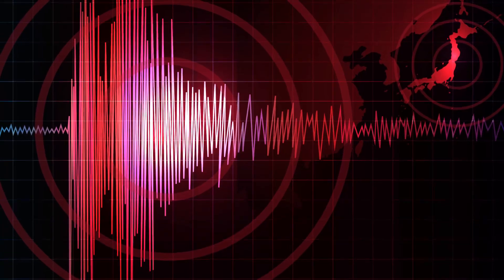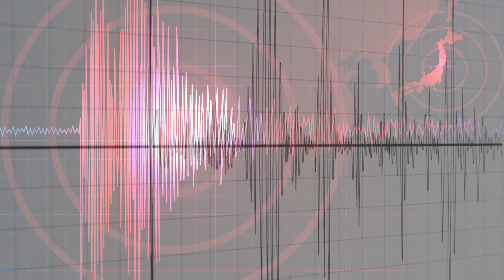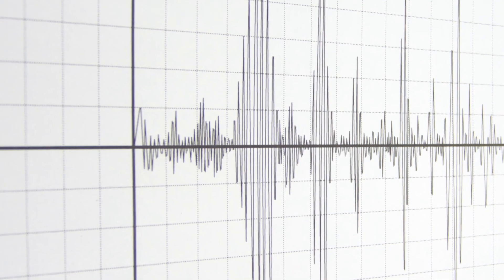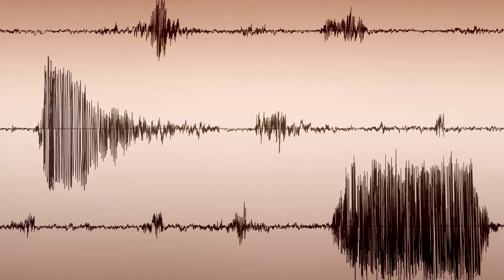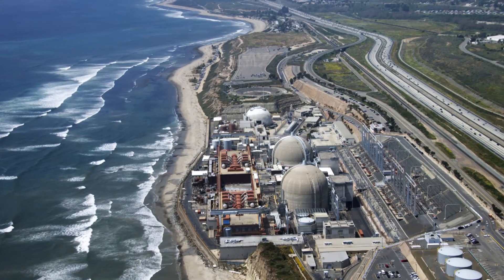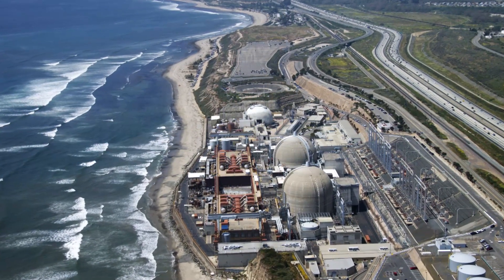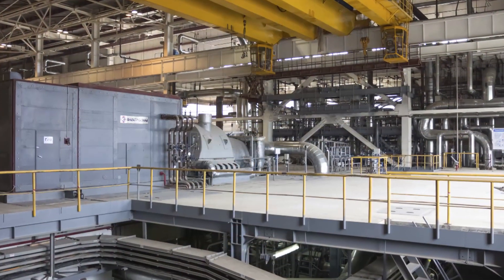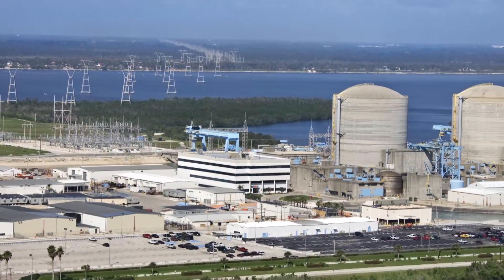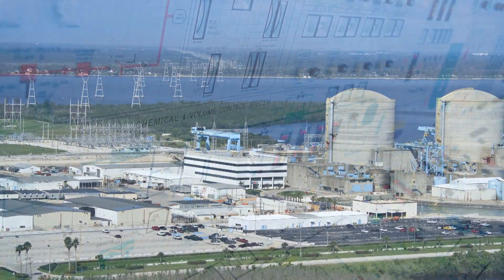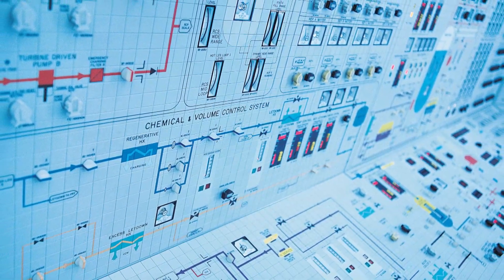Earthquakes come in a variety of different sizes and characteristics. Some of them shake back and forth about one or two times a second, others shake back and forth much more rapidly, say 20 times a second or 10 times a second. Those kinds of motions have a different impact on the plant. The ones at very low frequencies have large displacements, and so they tend to lead to stresses in buildings and piping. The high frequency kind have very low displacements, and so they're not damaging to the buildings, but there's some chance that they might cause small electrical components to misoperate.